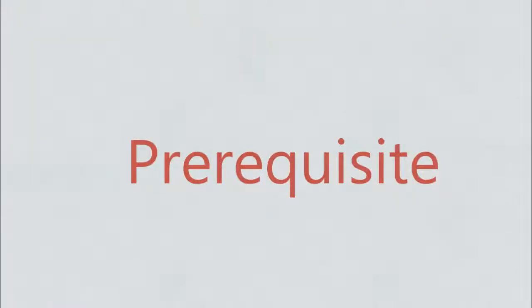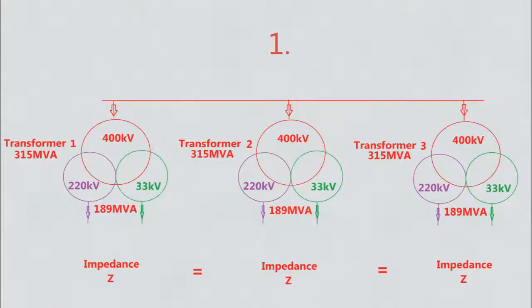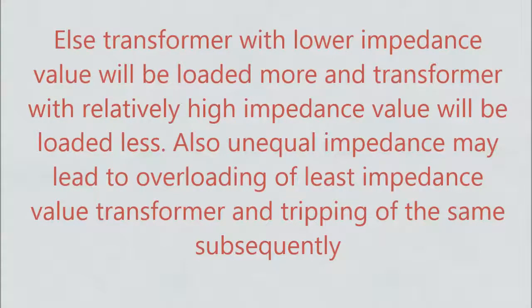Let's look at the prerequisites of transformer parallel operation. The most important condition is that all the transformers should have the same impedance value so as to share equal load. Otherwise, the transformer with lower impedance value will be loaded more and the transformer with relatively high impedance value will be loaded less. Also, unequal impedance may lead to overloading of the least impedance value transformer and tripping of the same subsequently.